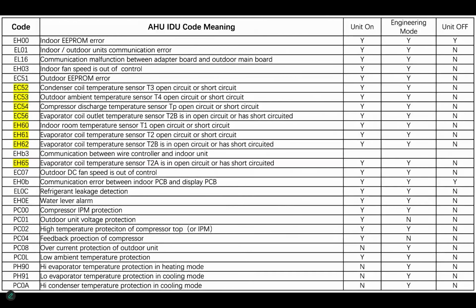Okay, so error codes. We'll start with these ones that are highlighted. These are all sensor errors. If one sensor fails, our system will actually continue to run. It manufactures a fixed temperature for that failed sensor, and it will continue to run. If a second sensor fails, it'll stop.